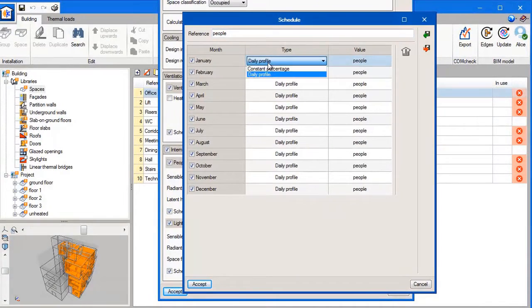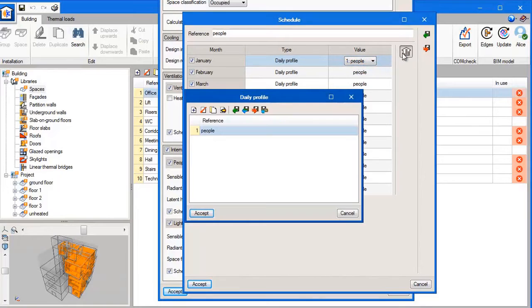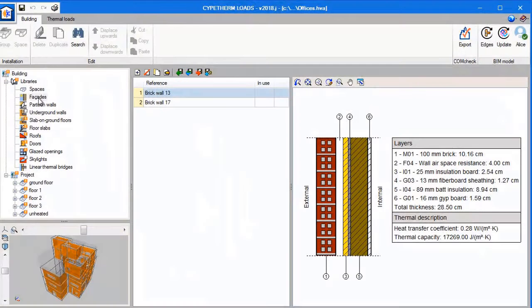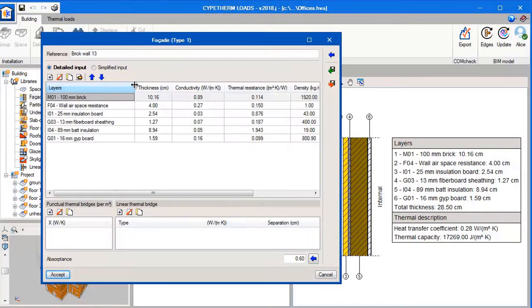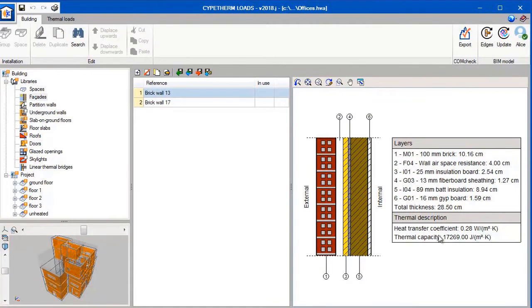We can define the schedules in two ways: as a constant percentage, or we can also create a daily profile. We can view the profile that we have created and edit it as we wish. Once we have finished with the spaces we can move on to the facades of the building. We can view the walls that we have created, and as you can see there is detailed information about each layer of the wall. The total heat transfer coefficient of the wall is automatically calculated, and this will be used to calculate the thermal loads in the building.